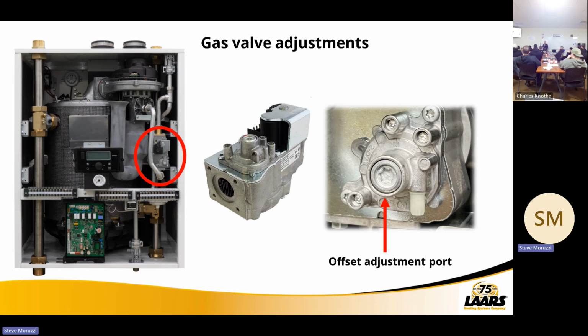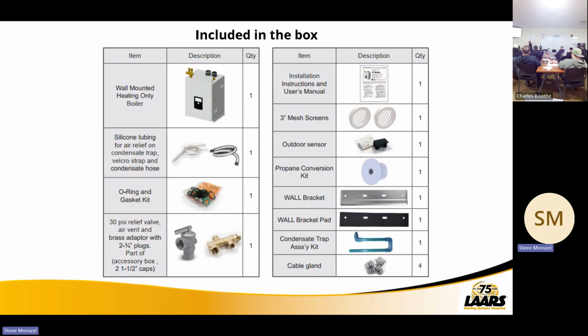Adjustments are made under the gas cap. That is a number 40 Torx bit cap. So you're gonna take that cap off and then you'll have an adjustment set screw in there with a number 40 Torx bit. What's included is the mounting bracket for the wall. That comes with both, when it comes with all boilers. So that's the mounting bracket and wall pad. That's really a vibration eliminator shown here on the right-hand side.